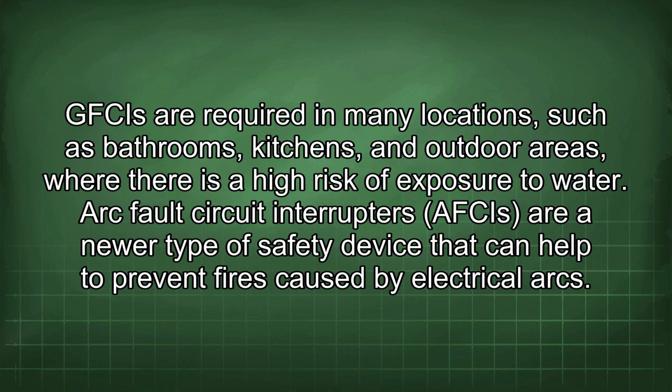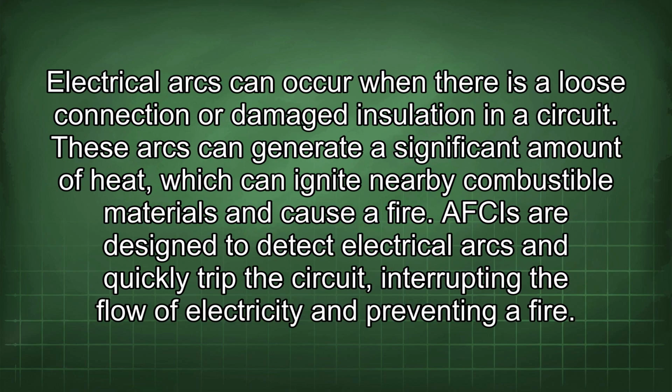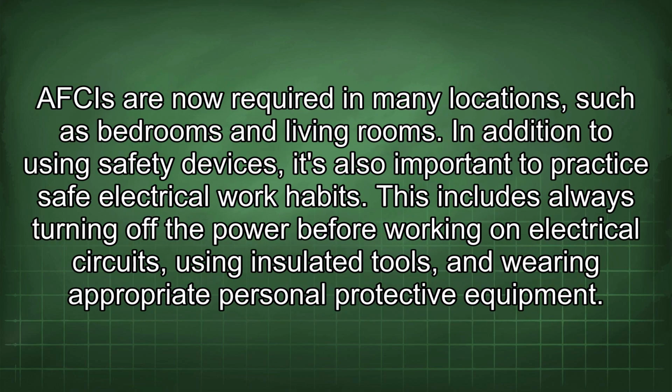Arc fault circuit interrupters (AFCIs) are a newer type of safety device that can help to prevent fires caused by electrical arcs. Electrical arcs can occur when there is a loose connection or damaged insulation in a circuit. These arcs can generate a significant amount of heat, which can ignite nearby combustible materials and cause a fire. AFCIs are designed to detect electrical arcs and quickly trip the circuit, interrupting the flow of electricity and preventing a fire. AFCIs are now required in many locations, such as bedrooms and living rooms.